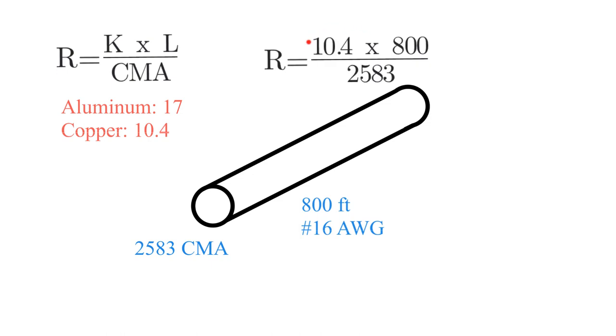So we plug all the numbers that we know into the formula: 10.4 is our K, 800 is our L, and our CMA is 2,583. Multiply those two, divide it by that, and we get a resistance of 3.22 ohms for that length.